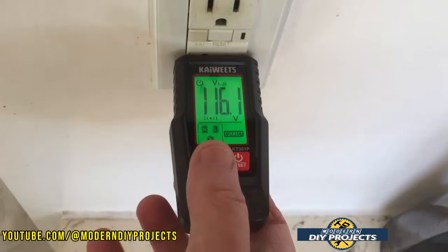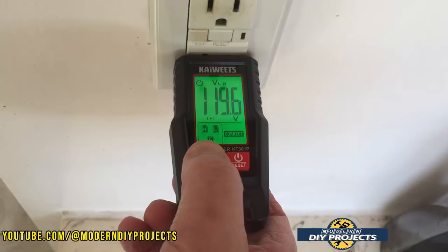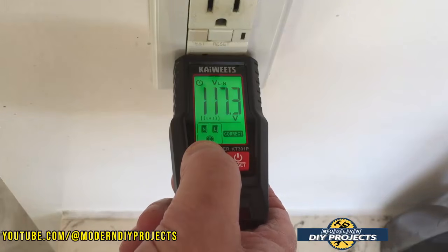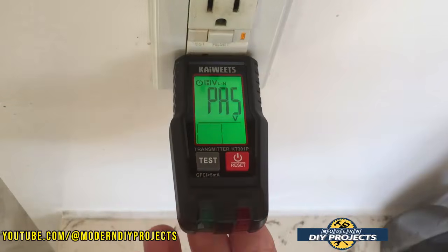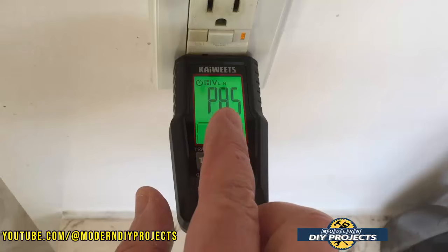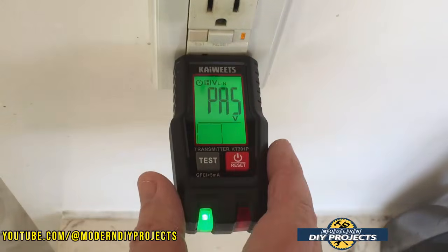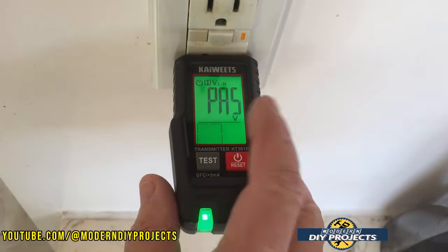So if we want to test it, all we do is hit the test button and hold it, and we'll see how it performs. And there you go, it shows you right there that it clicked everything off, but it says pass. And you see right there, it tripped. So the GFCI works perfectly fine.